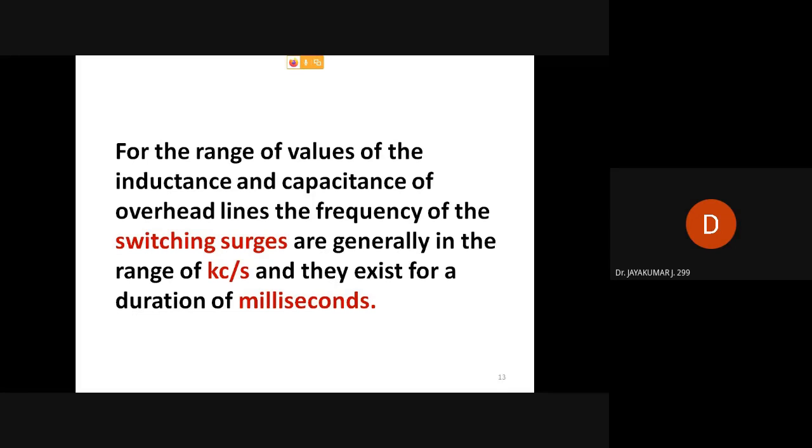The same way, with such overvoltage lasting a small, millisecond duration, your transformer winding may carry such a huge current as well as huge voltage for a millisecond. If it is more than that, maybe 1 second or 1.5 seconds, my transformer windings will burn. Overheating will take place, it will evaporate the transformer oil, and the winding will lose its insulation, and short circuit takes place.